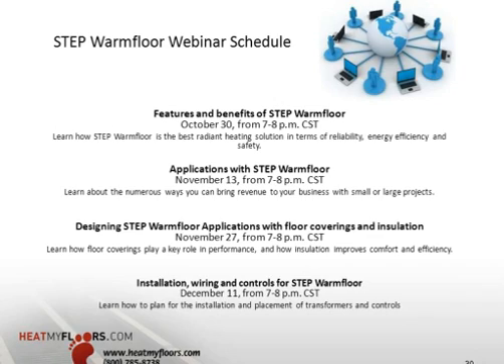When do I need a thermostat is a question that came up. I guess basically you want to use the thermostat where you want to control the temperature a great deal. Now, from my personal experience, I have 2 bathrooms that are on 1 transformer, and I elected not to use the thermostat. I let the elements self-regulate and let them heat. Once the temperature comes up to temp, it is using very, very little energy to maintain temperature. A lot of people, like with cable systems, will always use a thermostat because they're not self-regulating. They need a method of controlling their heat, whereas Step Warmfloor has the ability to self-regulate.